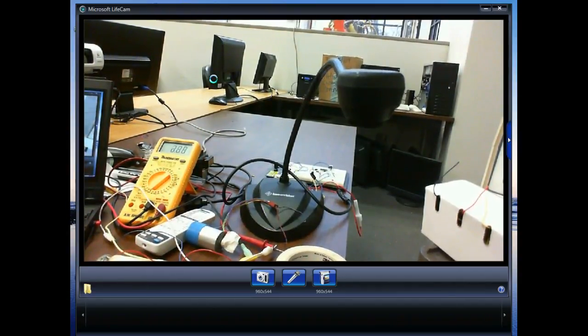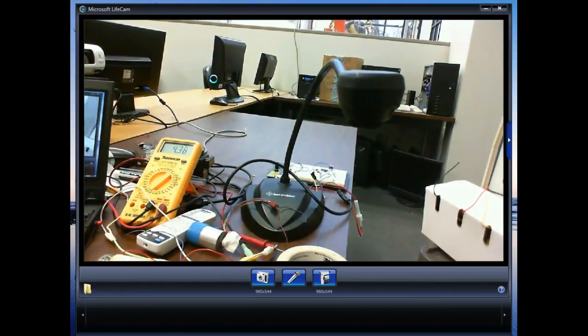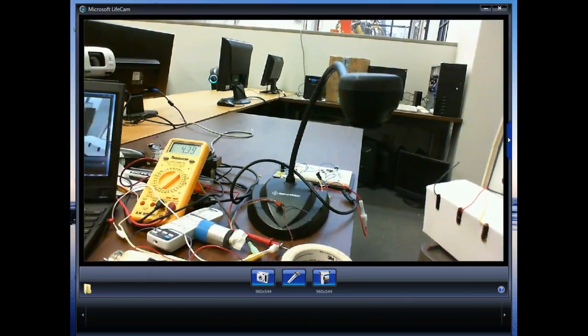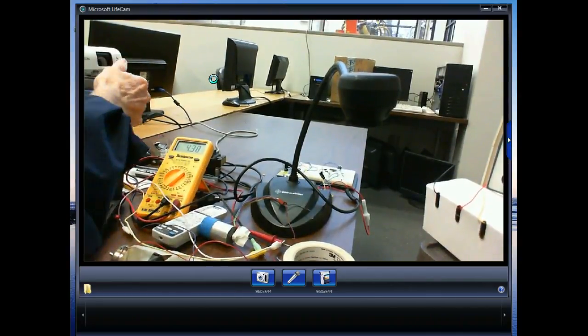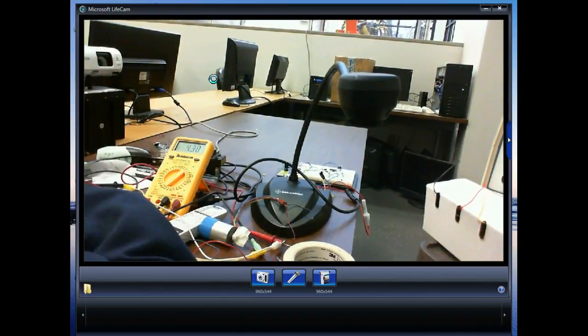What we would do here is use a pot. I could come up here and set it to 100, and that 100 generates a voltage. This goes into what we call an error amplifier. If the set voltage and the feedback from the tach generator don't match, it'll adjust the speed of the motor to run at the set speed. Okay, y'all understand that? Another thing that's very popular is devices that we refer to as encoders.